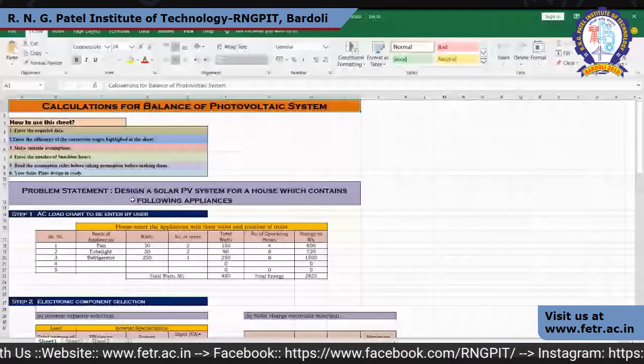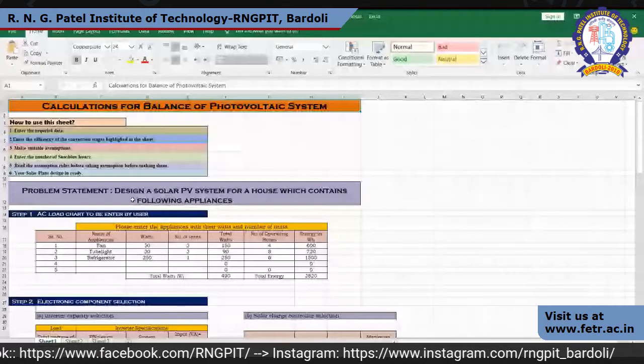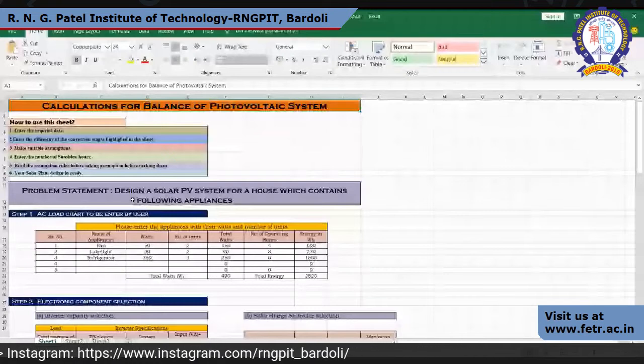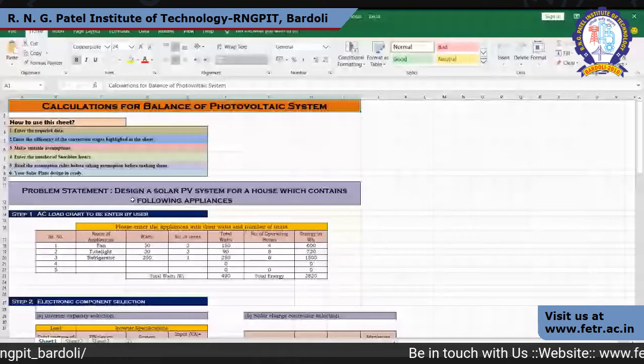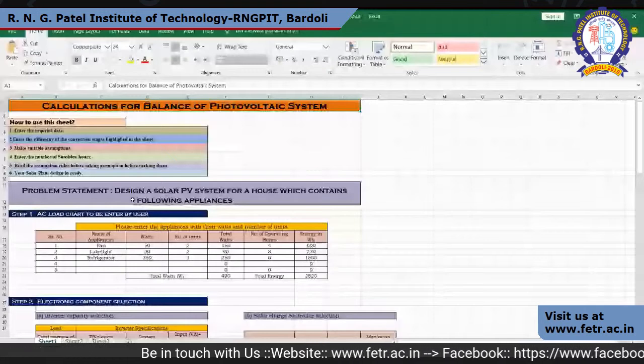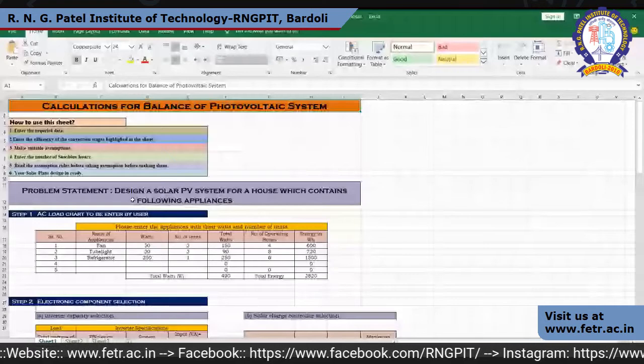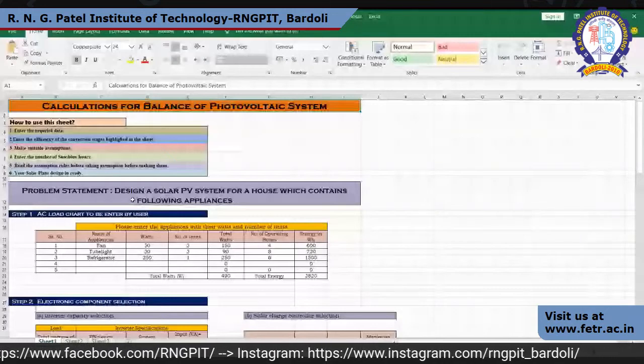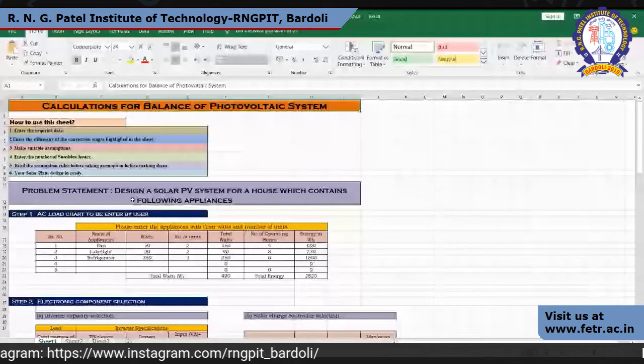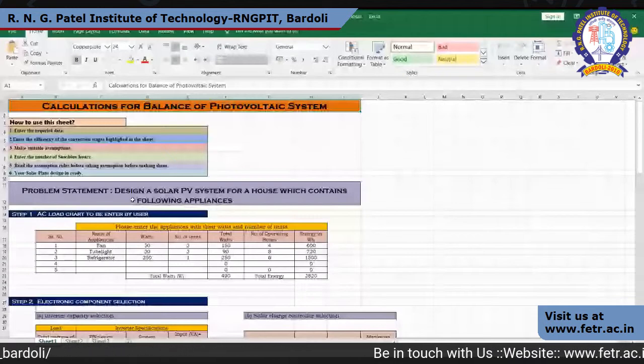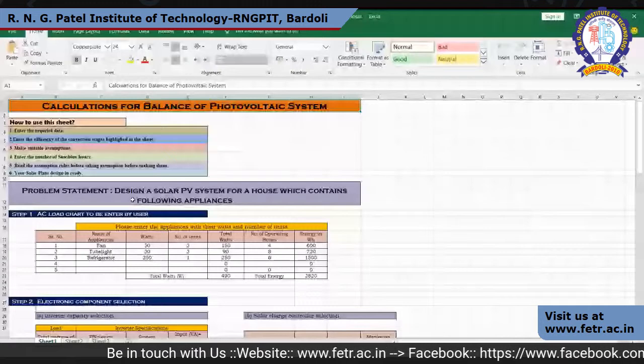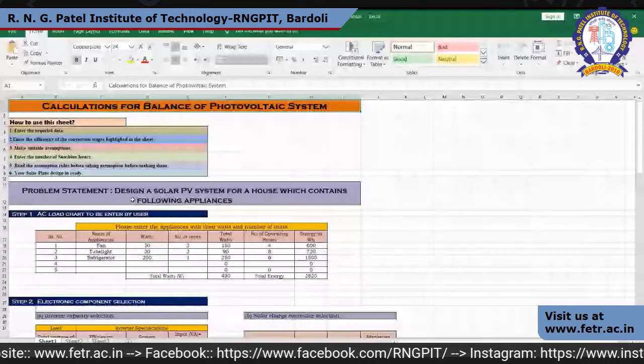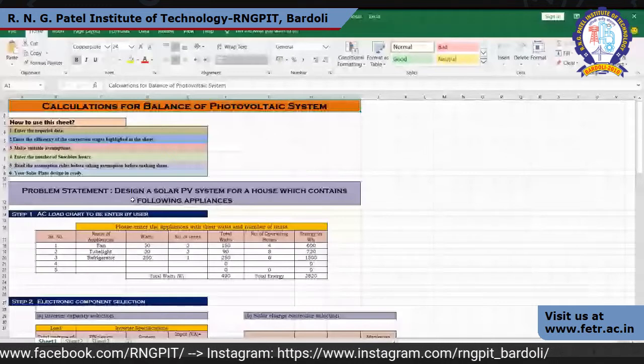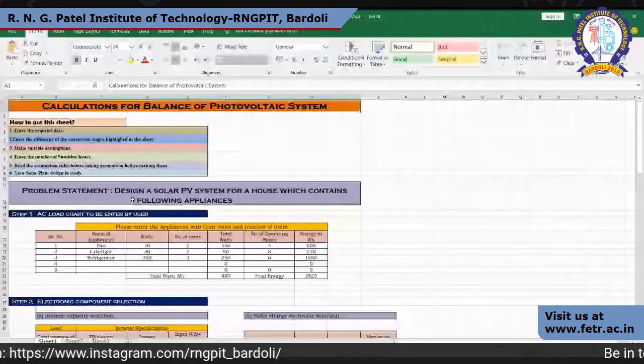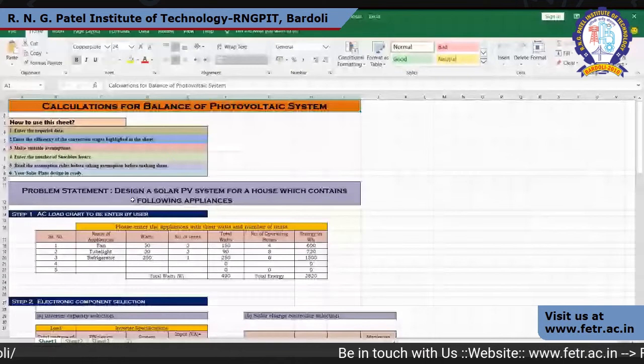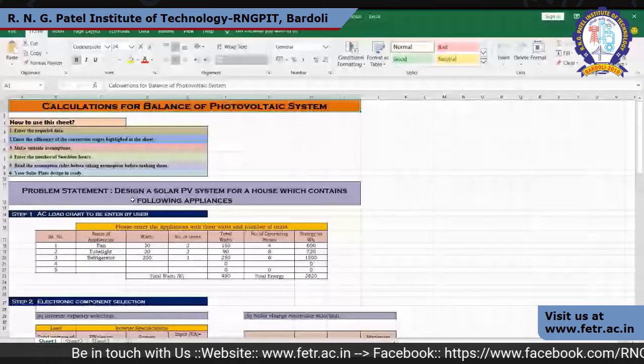We require an inverter, so the voltage we are calculating here is AC voltage. Power equals voltage into current. In the DC system at home, we can have a DC load or AC load, more or less at unity power factor. So we will assume 96% efficiency of the inverter. We have the KVA capacity as per the load requirement. Similarly, we can do it for the energy calculation. For good design, ultimately we go for the same efficiency in both power output and energy.